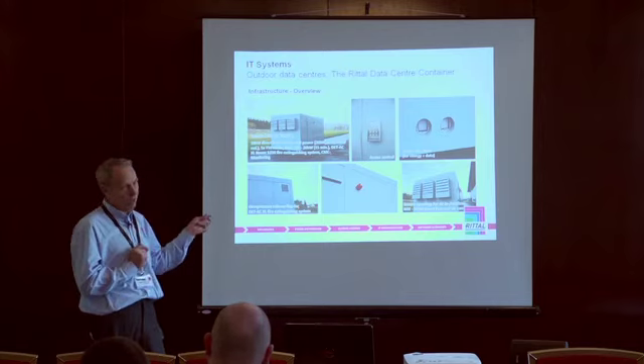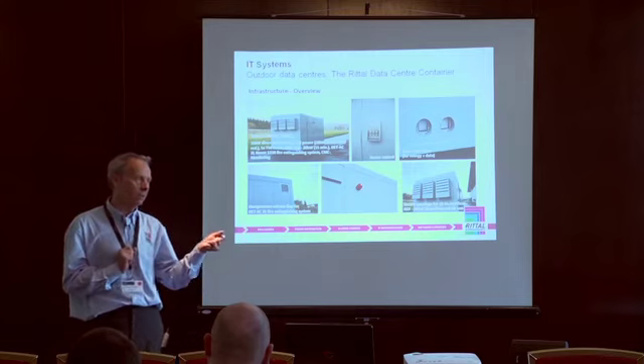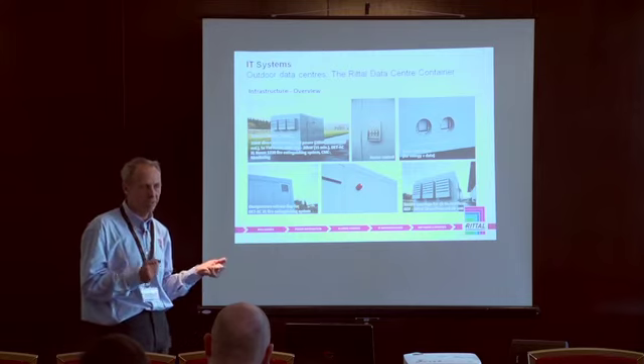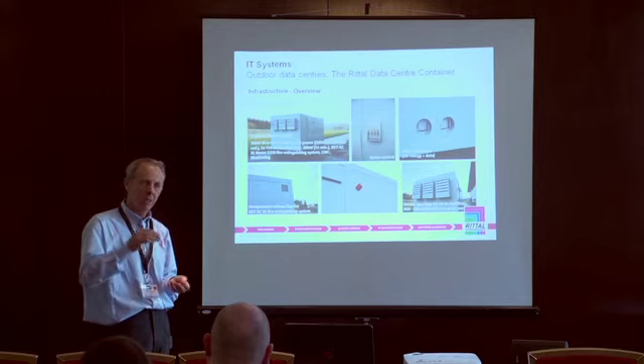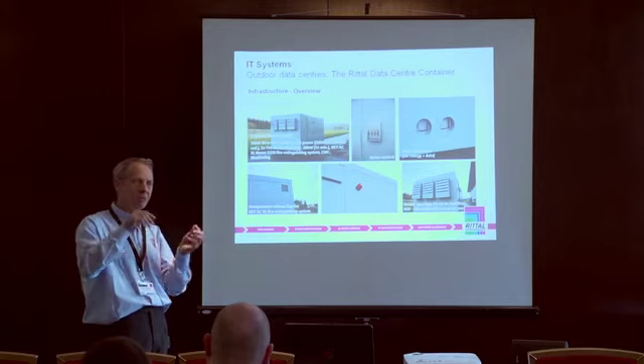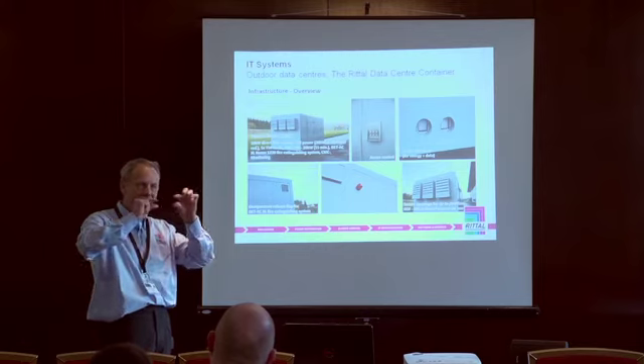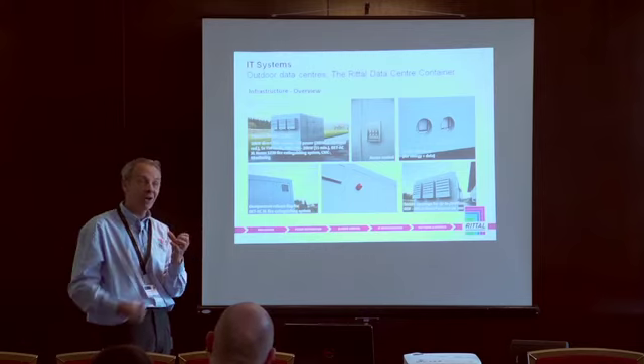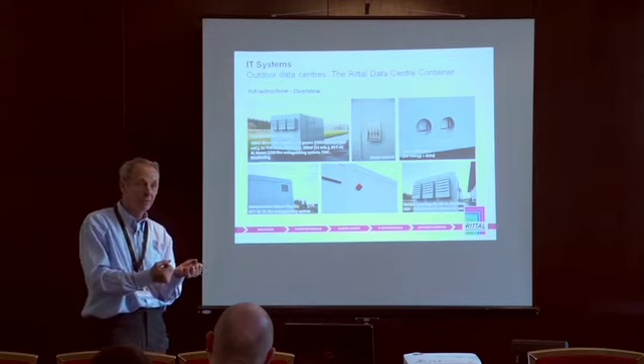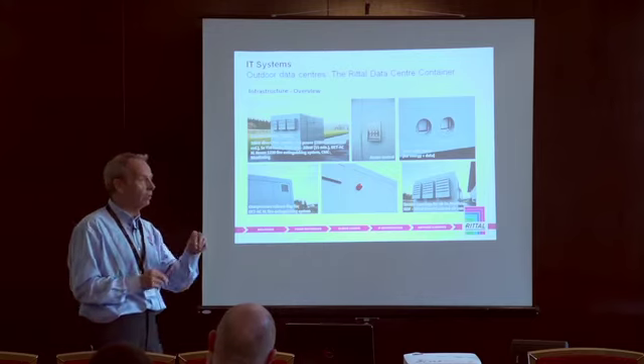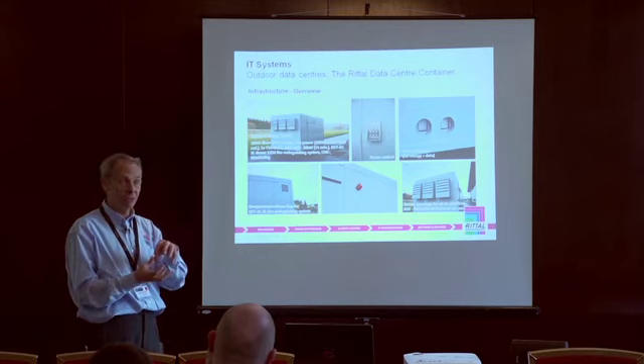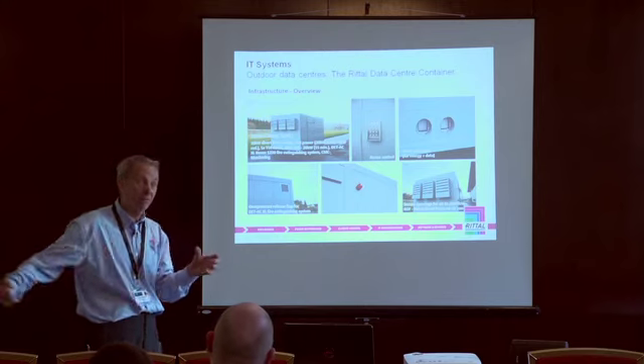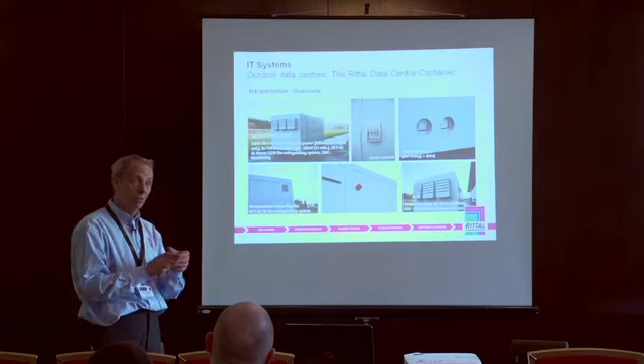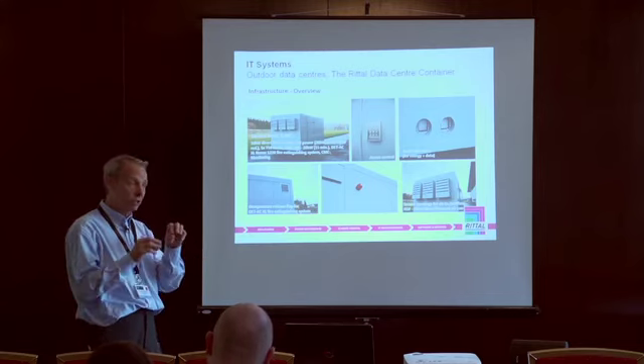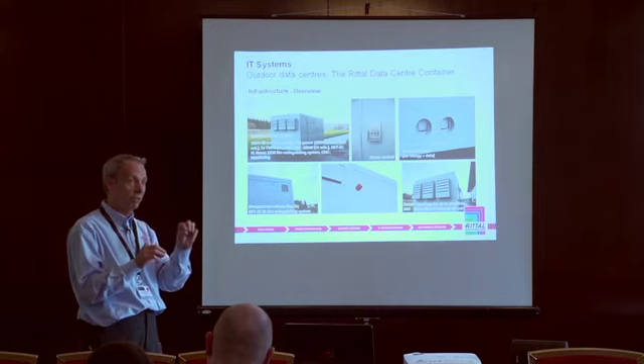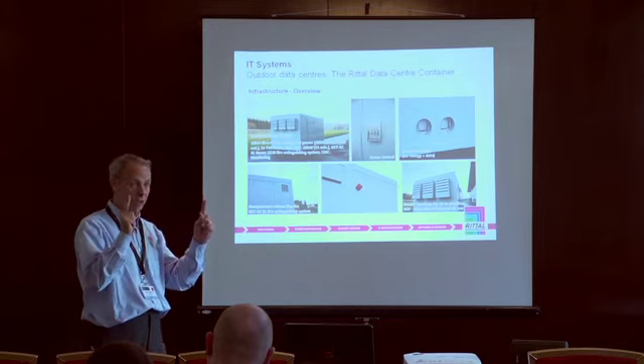The 1U platform system is normally Novec 1230, which is liquid until it hits the atmosphere and then becomes gas. The reason for it being in such a small platform is that liquid can be put into a much flatter platform - with gas you have to give it a clout to get it out. Normally only about 8% of the mix in a fire suppression cylinder is actual suppressant, the rest is propellant to push it into the space. The beauty of the Novec system is you can use a much smaller cartridged area - a 47U rack can actually be covered with a 1U platform system.